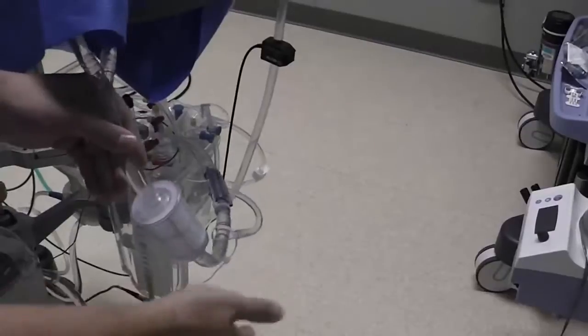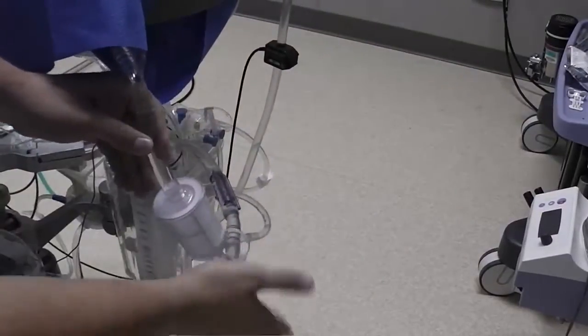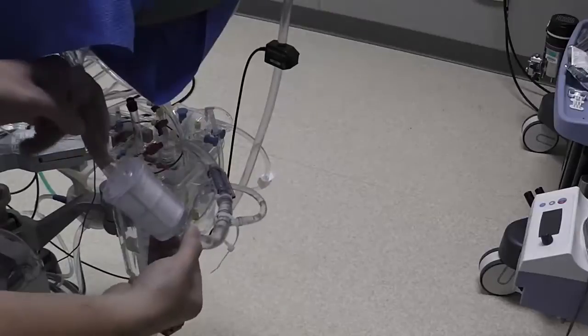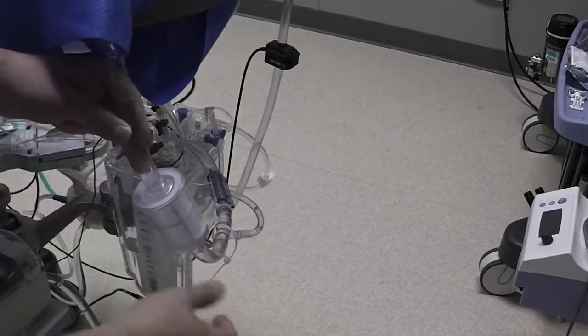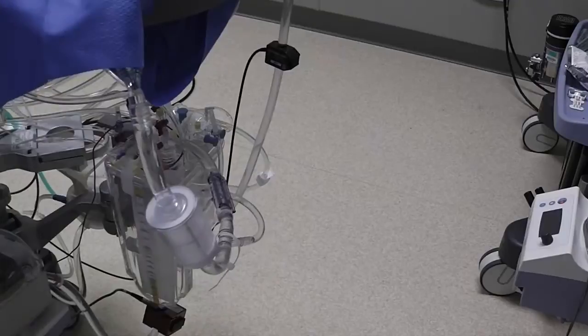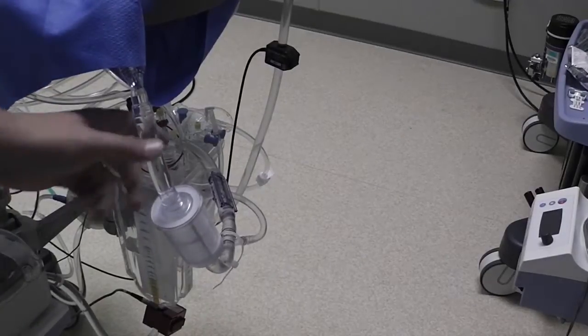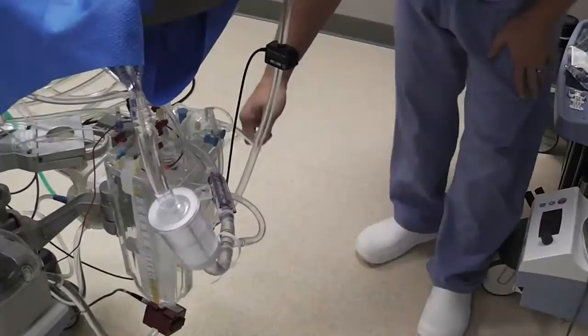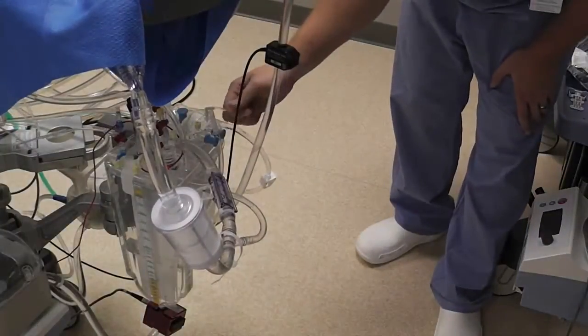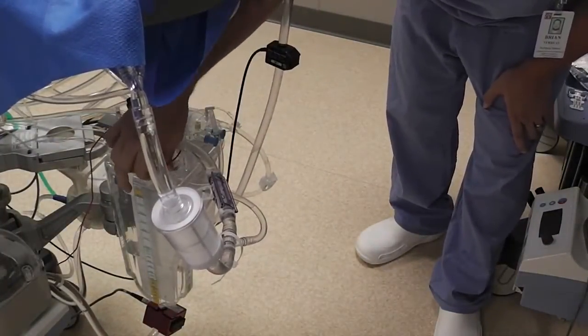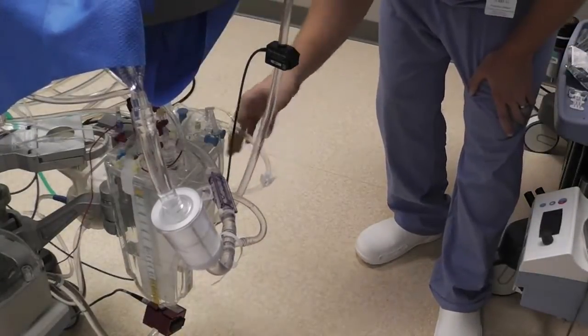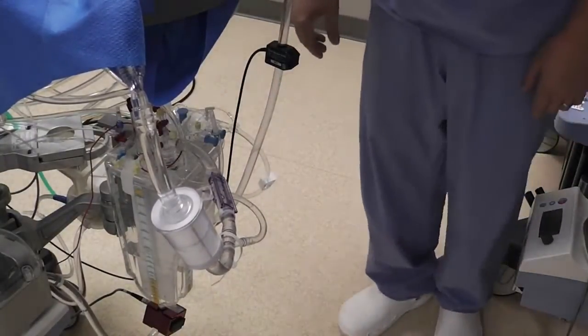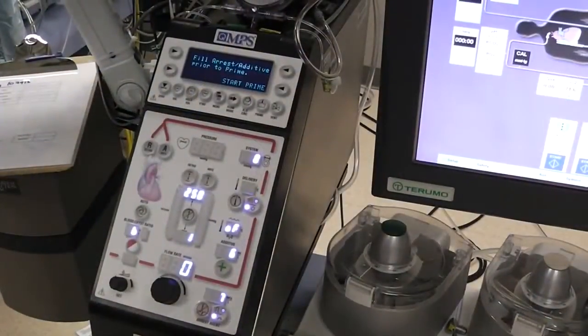I'm going to try to get some air out of this line here. You can kind of smack on this all day and you're going to get air out of this pre-bypass filter, but just kind of get the majority of the air out of there. And now I'm going to go to the back, open up the recirc line, open up the oxygenator purge, and open up my manifold here to let those prime up. Then I'm going to come back over to the Quest. Alright, back over at the Quest here, I'm simply going to hit Start Prime, and that will start it doing its thing.